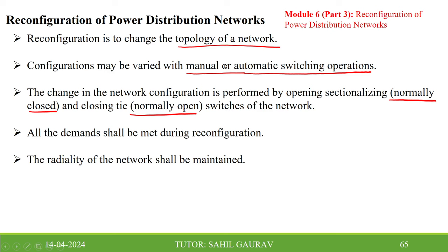Now the next module is the reconfiguration of power distribution network, which also comes under power distribution planning. Reconfiguration is to change the topology of the network. We are not developing a brand new network. The configuration may be varied with manual or automatic switching operations, and the change in network configuration is performed by opening or closing sectionalizing switches of the network.